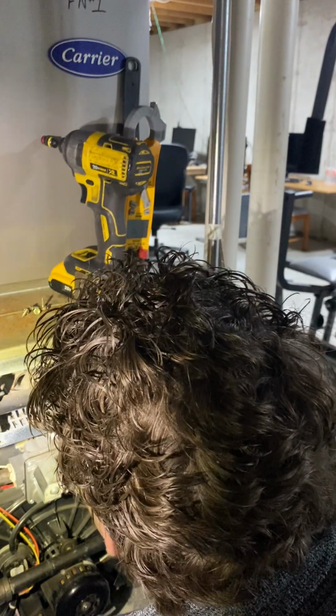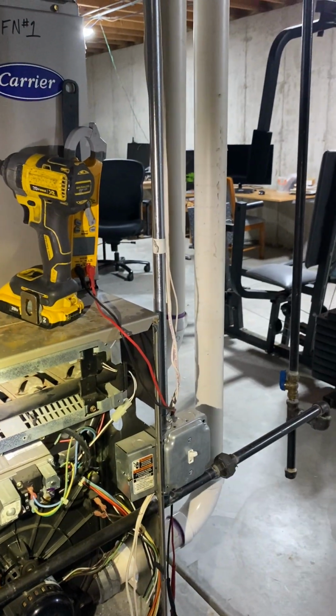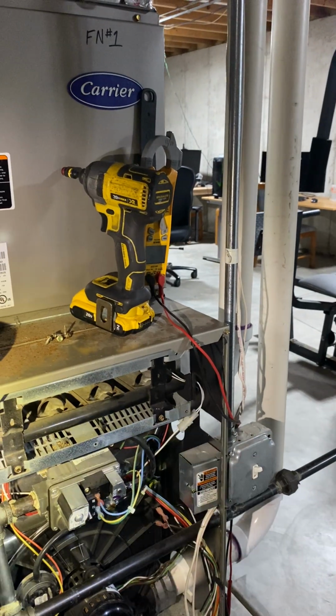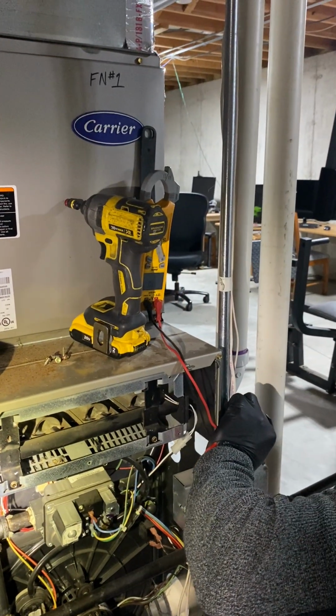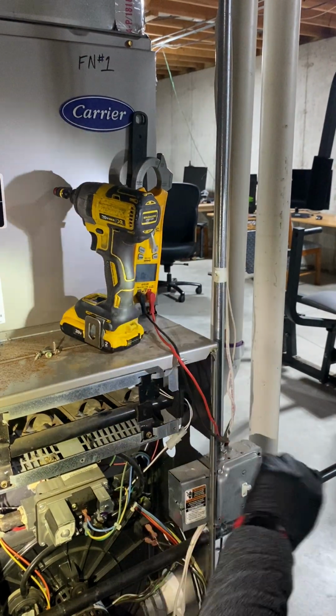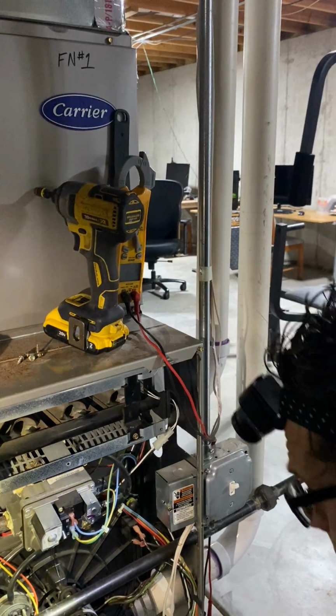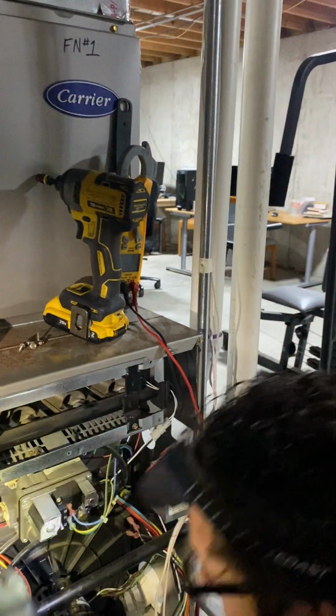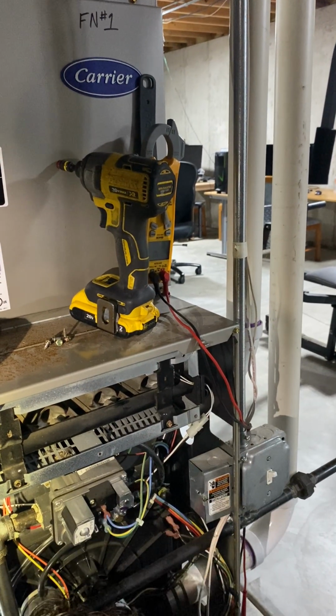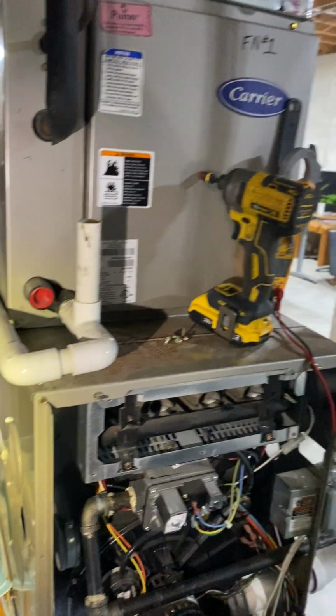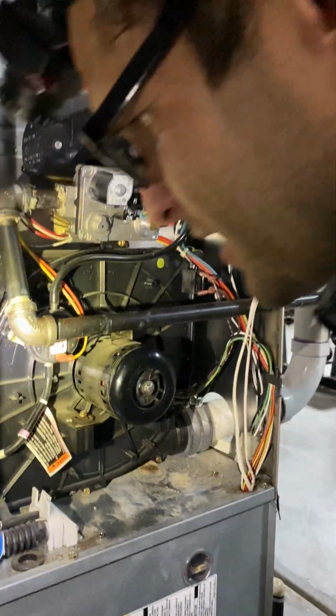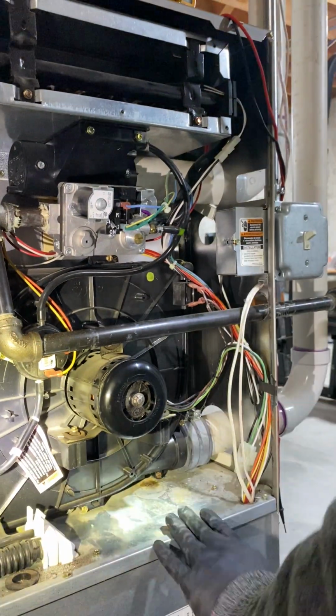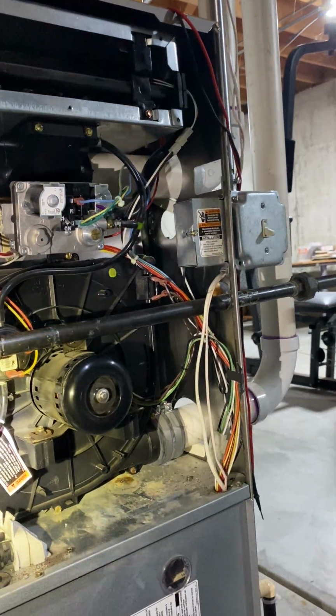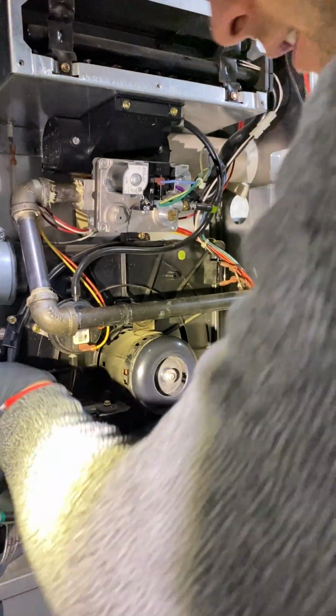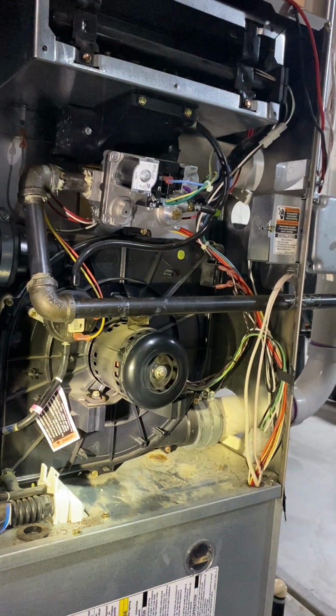Exchangers don't smell good. Usually, now we know the pressure switch is not pulling in. Gotta figure out why. It's filled with water. That's why. How did the water get in there? It's probably backed up in your P-trap. So it's not pulling in this pressure switch because it is filled with water.